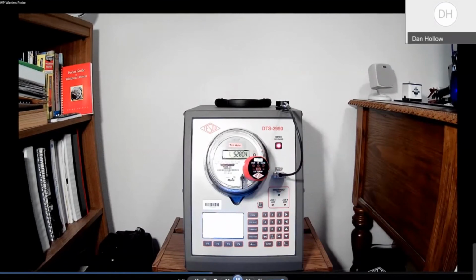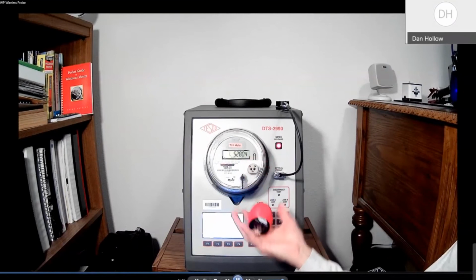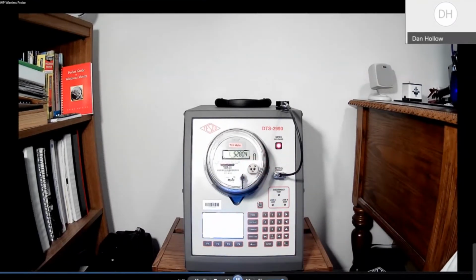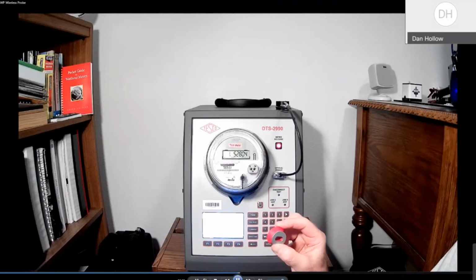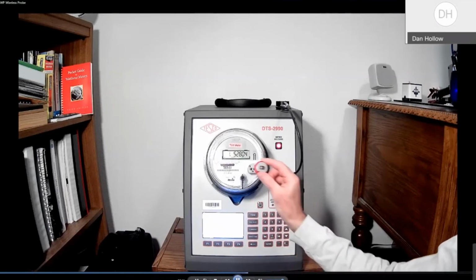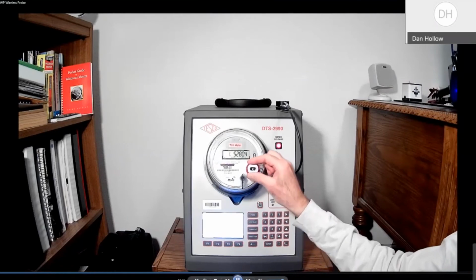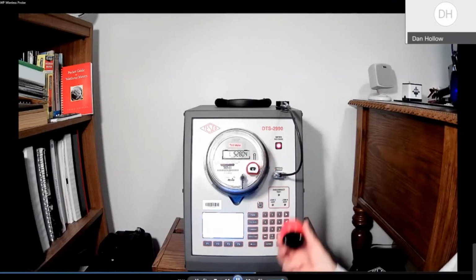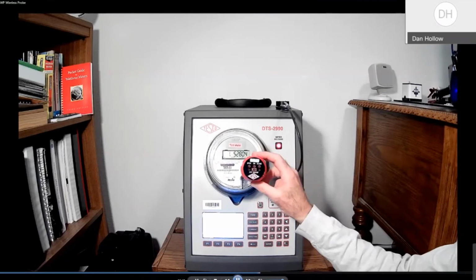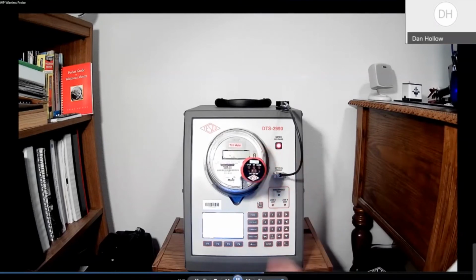I've done it many times, but it's more likely to fall off given a little bit of a push. So I'm going to use this 1041 adapter. This particular adapter was initially designed for meters that have just a circular plastic ridge that protrudes from the meter cover. In this case, I'm going to be using it as a standoff to get away from that demand reset. Now you've got a good firm connection here.